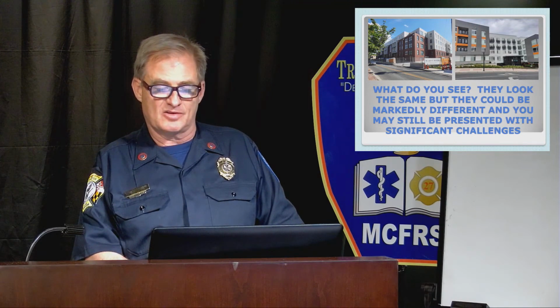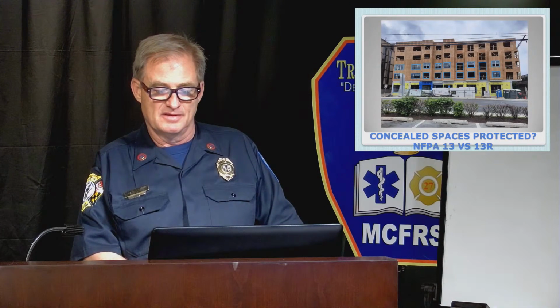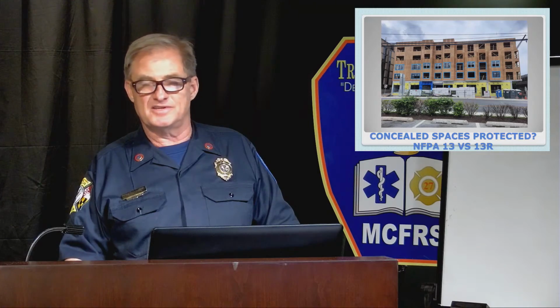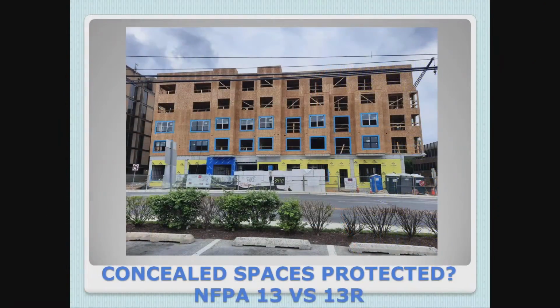So another question I get quite a bit is, what's the difference between an NFPA 13 system, which we call a fully sprinklered building, versus an NFPA 13R sprinkler? This building here, I don't know what sprinkler system it's getting, but it has a fairly small footprint. It is 4 stories on top of the concrete. You can obviously see the 4 stories on top of the concrete is wood. It will not surprise me if this is an NFPA 13R system, because one difference the code delineates is the NFPA 13 system, you can build the building bigger without firewalls. You can't do that with an NFPA 13R system. But this is a fairly small footprint.